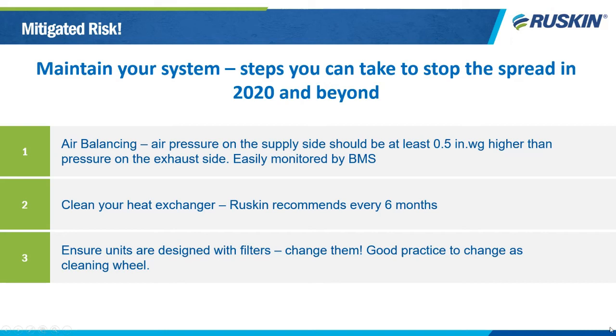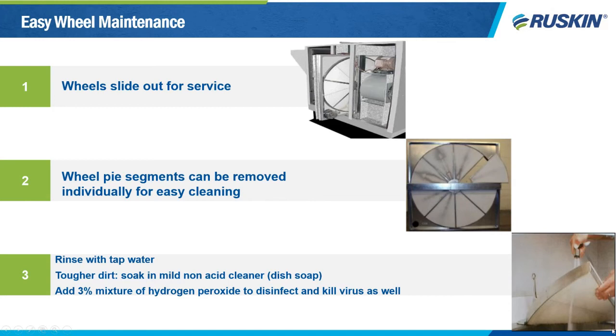Maintaining the wheel. So I have pictures of a wheel here. However, the core can be cleaned with very similar steps. So our wheel is on rails. It does slide out. You can take the whole wheel out to clean it, or the wheel breaks up into little slices of pizza. You can clean each piece of the wheel individually if you would like. We recommend cleaning the wheel with just tap water. What I usually see out in the field is you fill up a Rubbermaid container with some tap water, add household dish soap to it, let it sit for 5 minutes, and then soak that wheel again with the tap water to get it clean. With everybody hypersensitive about the virus right now, Air Exchange, who is our wheel manufacturer, recommends adding a 3% mixture of hydrogen peroxide to disinfect and kill the virus on the wheel as well.